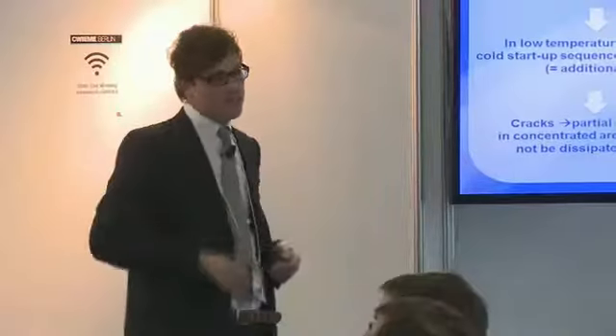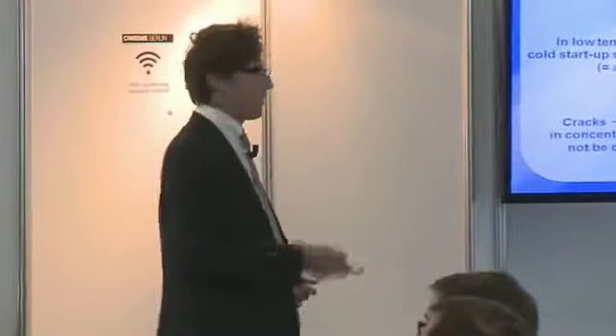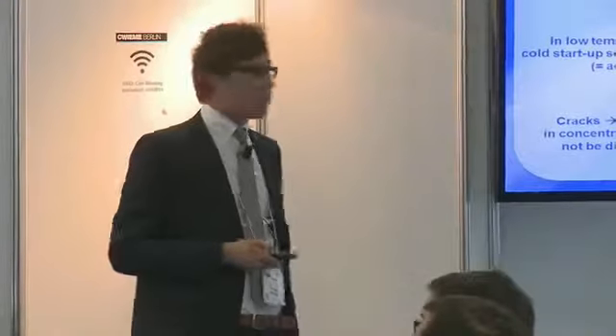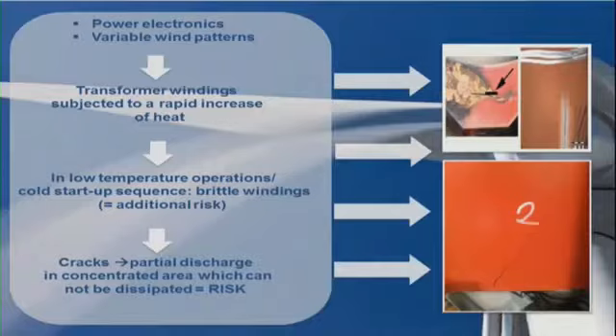Because of the variable wind patterns and also the brittle material, you can have cracks, some examples of which could lead to partial discharge in concentrated areas. This is again a risk for the transformer, so that's why we are testing and validating this in the laboratory.